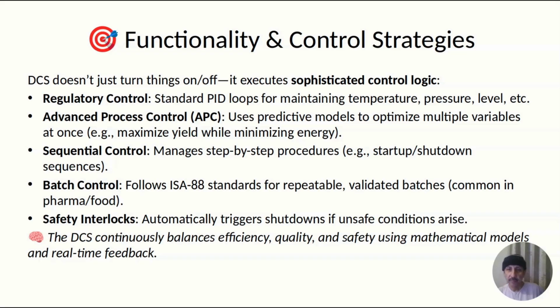For example, in a refinery, APC might adjust 50 valves simultaneously to maximize gasoline yield while staying within the safety limits. It also handles batch processes with strict sequences, which is essential in pharma, where regulatory compliance demands auditable, repeatable steps. And let's not forget safety interlocks. If pressure exceeds the threshold, the DCS can trigger an emergency shutdown faster than a human ever could.